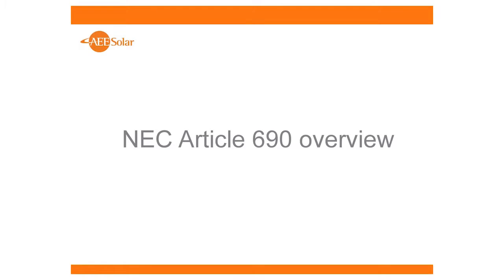piece of electronics, and then we have this DC circuit, which the 2017 code has actually gone into and defined, that we have PV source circuits and we have DC to DC converter source circuits. And there's things that apply to both of those types of circuits, and then we have PV system DC circuits now, which is a term that covers all DC circuits that would happen in a PV system, which would include PV source circuits as well as DC to DC converter circuits, because there's some things that apply to all of them, and some only apply to ones that are driven by PV specifically. Okay, because when they're driven by PV specifically, we have to worry about all those differences that are in those IV curves that we talked about. Okay. So we've got lots of parts of the code that apply.